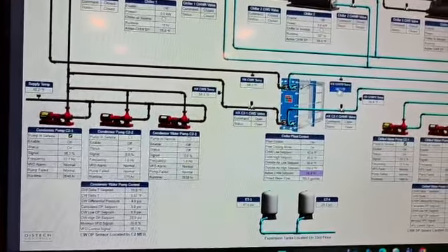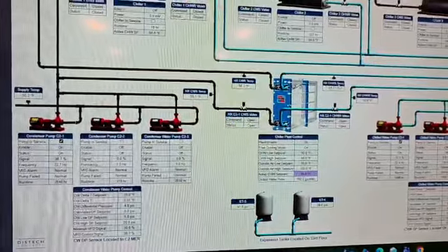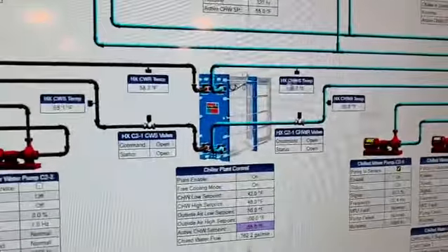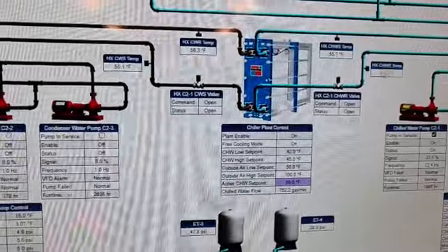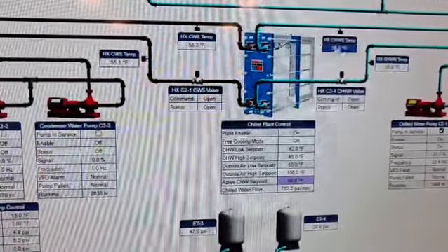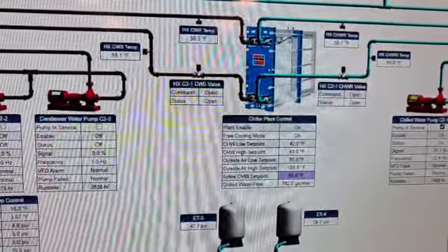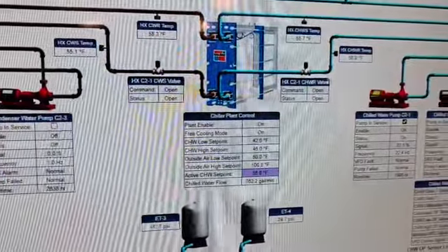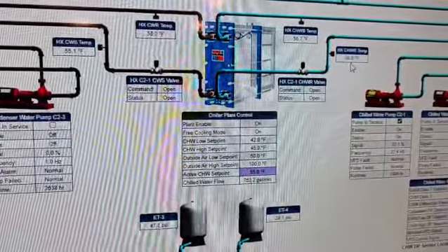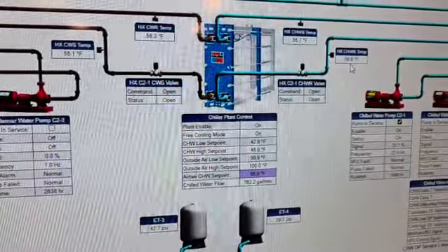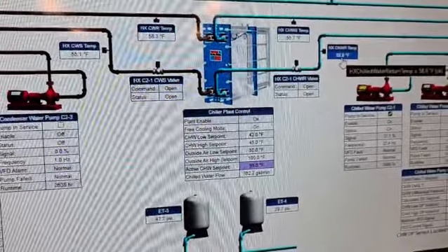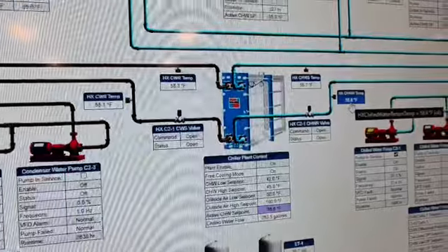And then you have your sensors, HX chilled water supply temp. This is what you supply into the building, 57. And this is your water coming after it went through all the building, right? This water went up, went through all the units and came back. It only rose 1 degree because there's nobody asking for cooling at this point, or few people asking for cooling.